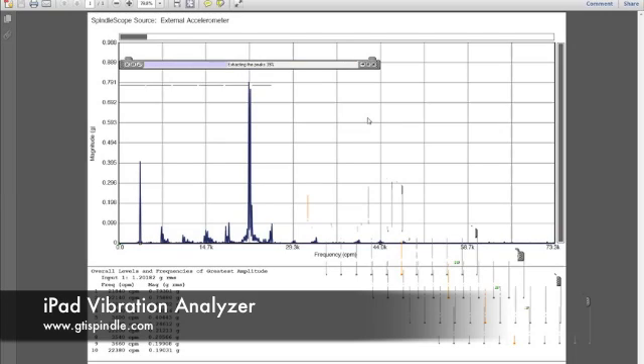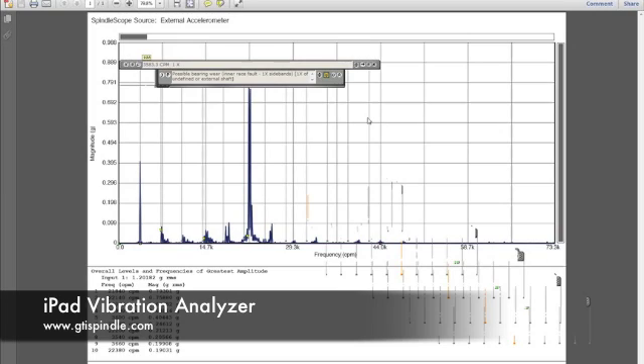And as you can see, it's extracting the peaks, and when it's done, it builds a pattern. And here it says possible bearing wear. And I know this to be true because I know the motor I measured.